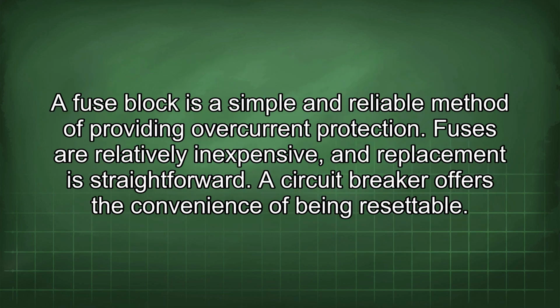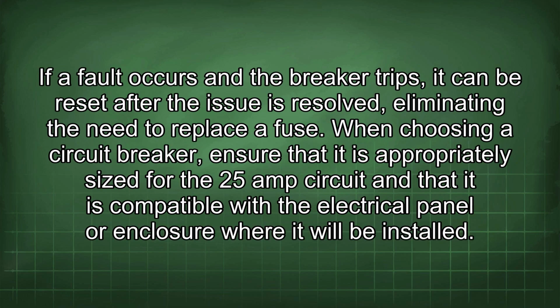A fuse block is a simple and reliable method of providing overcurrent protection. Fuses are relatively inexpensive, and replacement is straightforward. A circuit breaker offers the convenience of being resettable. If a fault occurs and the breaker trips, it can be reset after the issue is resolved, eliminating the need to replace a fuse. When choosing a circuit breaker, ensure that it is appropriately sized for the 25 amp circuit and that it is compatible with the electrical panel or enclosure where it will be installed.